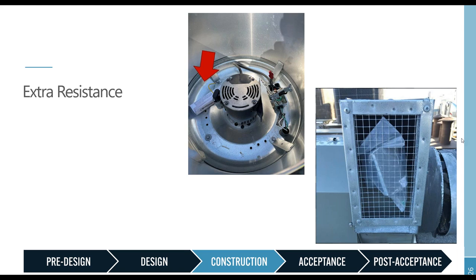Anyway, best case scenario is this debris makes an obnoxious noise, keeping building occupants up at night or giving them something to complain to building engineering. Worst case scenario is it gets lodged into your fan motor and causes some serious damage, smoke, fire, nothing anybody wants. For this reason, we always make sure to stick our heads into the nooks and crannies just to double check.